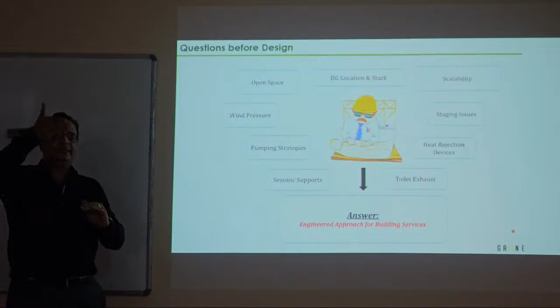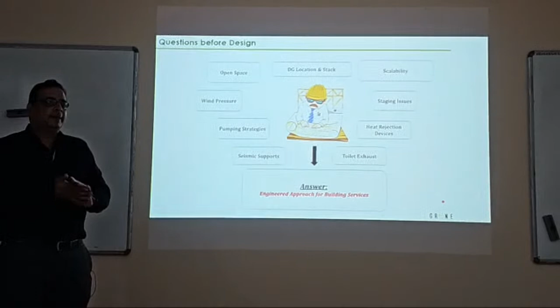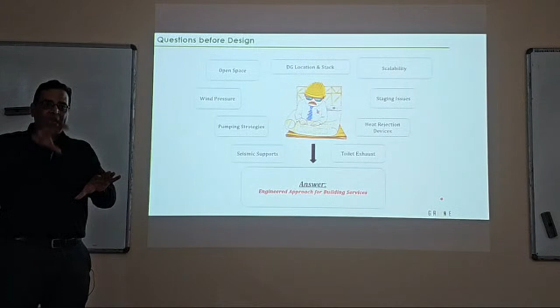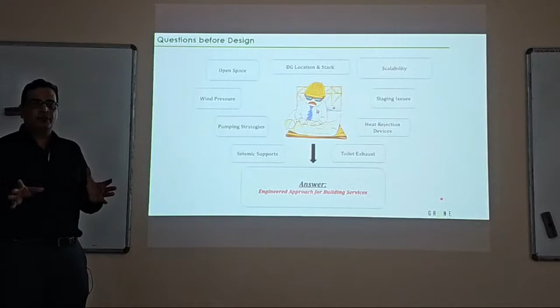The position of the DG location in a commercial building, very specifically, where you are doing 100% backup, where power is an issue, you do 100% backup. In commercial urban cities like Mumbai, Bangalore, any city, the expectation of 100% backup power is a must. That means even if I consume transformer's electrical power, I still will provide 100% backup, because I am not willing to sacrifice even a day, 1 hour, or few seconds without power. Because the business will get impacted. Any business that gets impacted, the revenue of that business will come down. So they are stating a requirement that the building should have 100% backup.